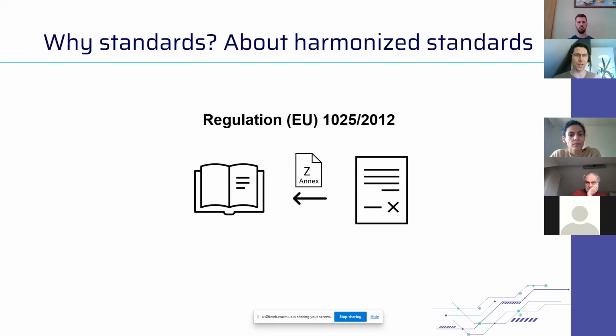It can tell you which of the general safety and performance requirements from Annex 1 can be satisfied with one particular standard and for which ones you need more. So having that Annex Z is very, very important. The problem is that this so-called harmonization is very, very impeded in the European Union, because the definitions and terms always need to be identical. Otherwise, especially from the legal perspective, somebody will challenge the validity of the standards against the legislation because they speak of different terminology. Yeah, of course. So the harmonization is a very difficult task.